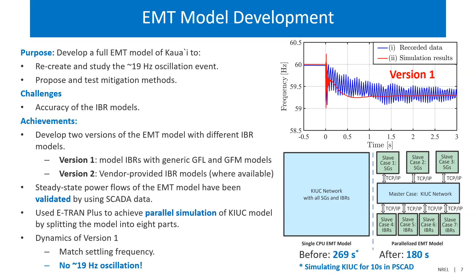The good news is we eventually received the vendor-provided model and connected it to our grid, hoping the magic would happen. Actually, still no 19 Hertz oscillations. We then realized the vendor-provided model didn't reflect the dynamic performance of the IBR in the field.